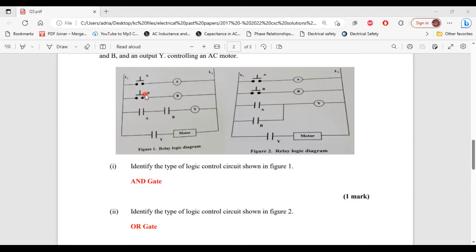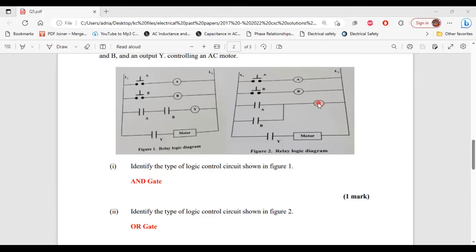For part two, identify the type of logic control circuit shown in figure two. That is an OR gate. When the push button labeled A is pressed, the coil labeled A will be energized as a result of a path for current to flow being created. When the coil is energized, anything labeled A in the circuit will be affected, so this normally open contact will now close. Once this contact is closed, a path for current to flow is created, and the coil labeled Y will become energized. Anything labeled Y in the circuit will also be affected, so this normally open contact will close — as a result, the motor will turn on.